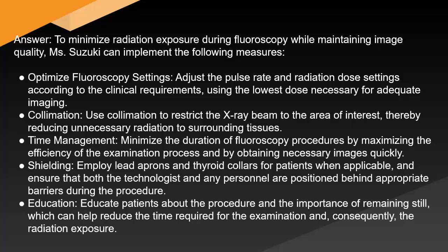Answer. To minimize radiation exposure during fluoroscopy while maintaining image quality, Ms. Suzuki can implement the following measures. Optimize fluoroscopy settings. Adjust the pulse rate and radiation dose settings according to the clinical requirements, using the lowest dose necessary for adequate imaging. Collimation. Use collimation to restrict the X-ray beam to the area of interest, thereby reducing unnecessary radiation to surrounding tissues.